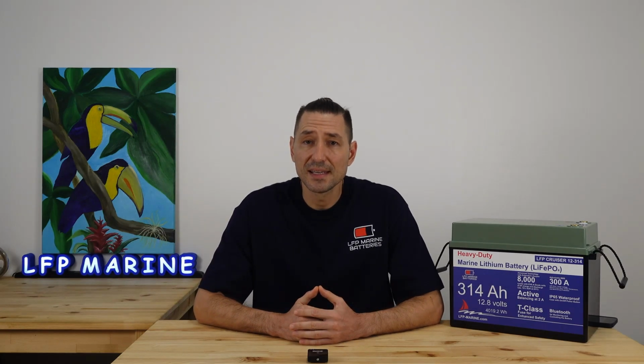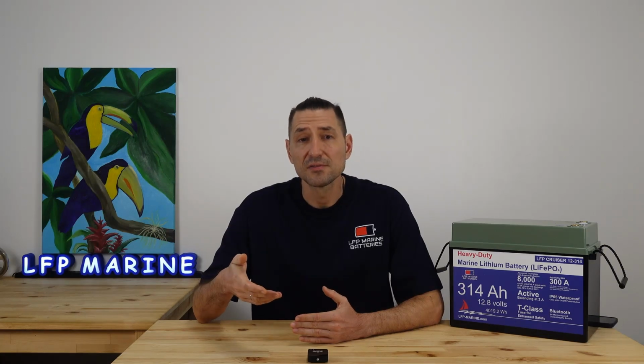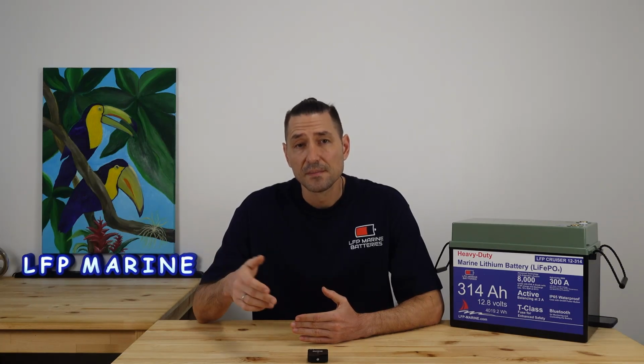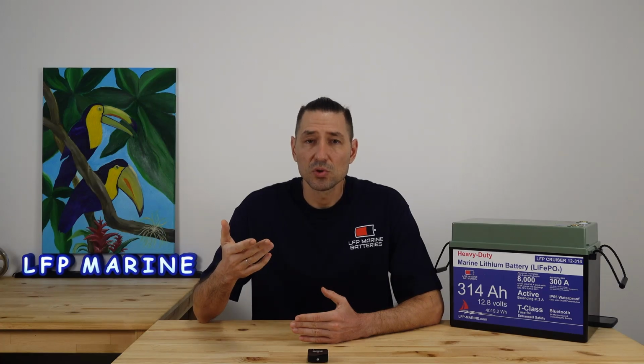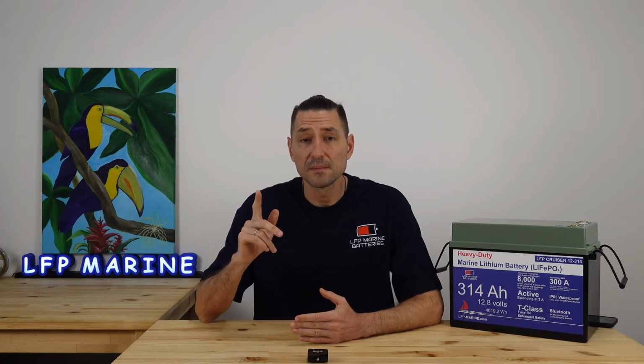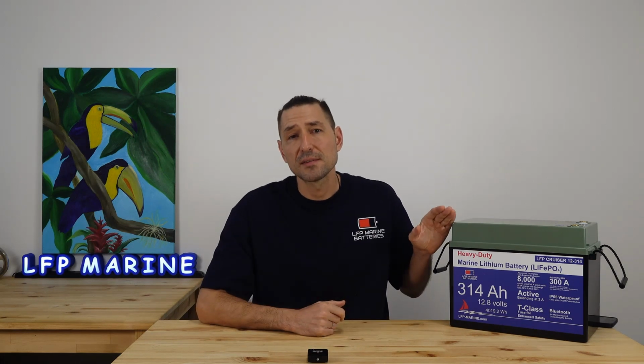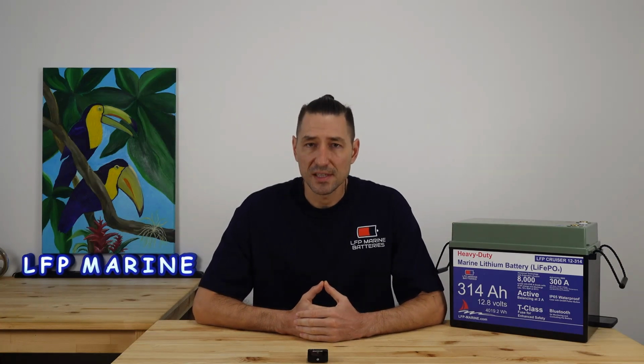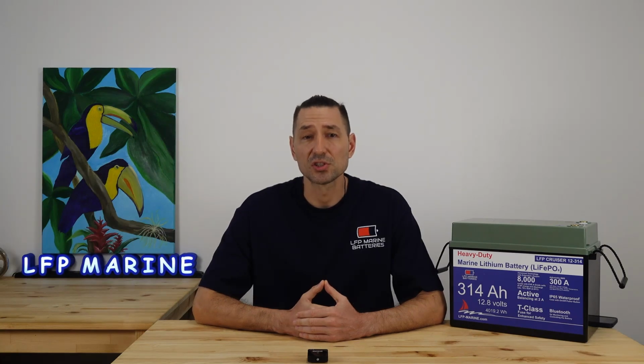At sea, an incident may occur in which part of the battery, for example, the BMS itself, is physically damaged. In this case, there will no longer be any short-circuit protection. That's exactly why we specifically added a fast current limiting fuse of the T class to our battery, as a 100% guarantee of short circuit protection even in emergency situations.